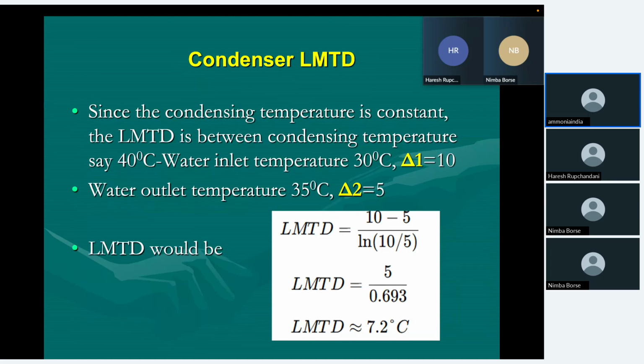Since the condensing temperature is constant, LMTD, as I told you, for 40 degrees condensing temperature and with water inlet temperature of 30 degrees centigrade, delta T1 will be 10 degrees centigrade and delta T2 will be 5 degrees centigrade. So LMTD will be 7.2 degrees centigrade.